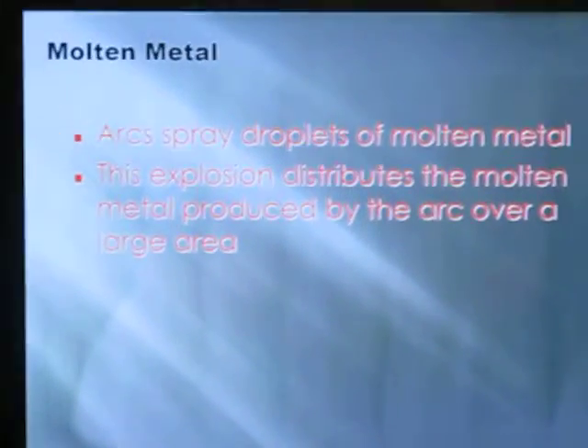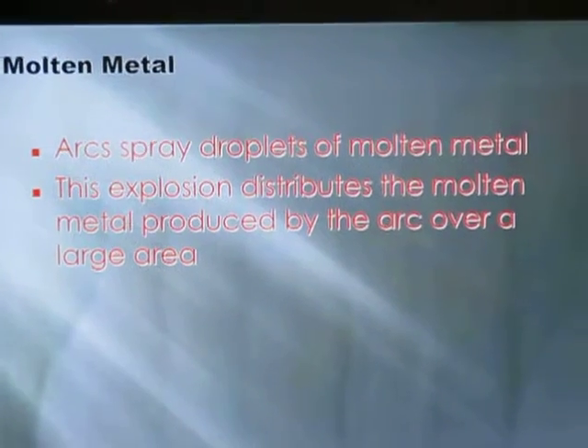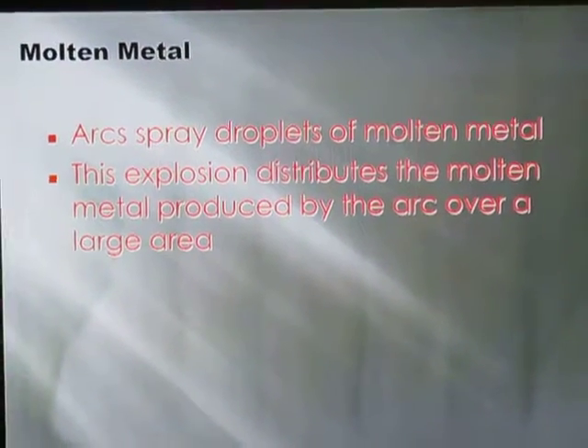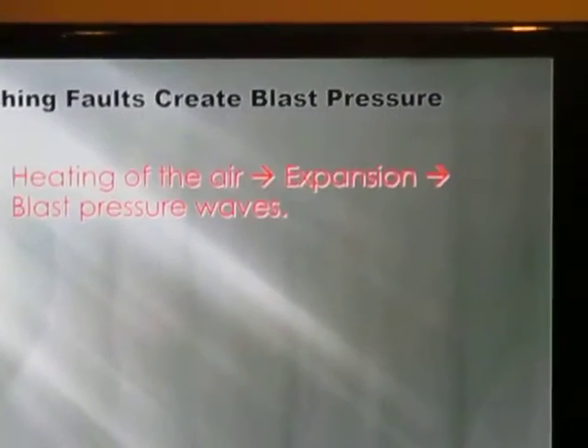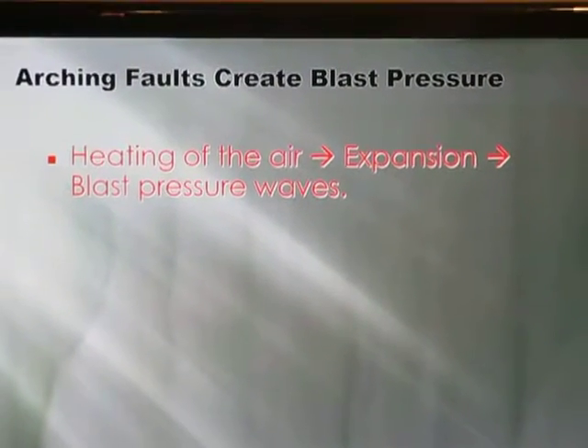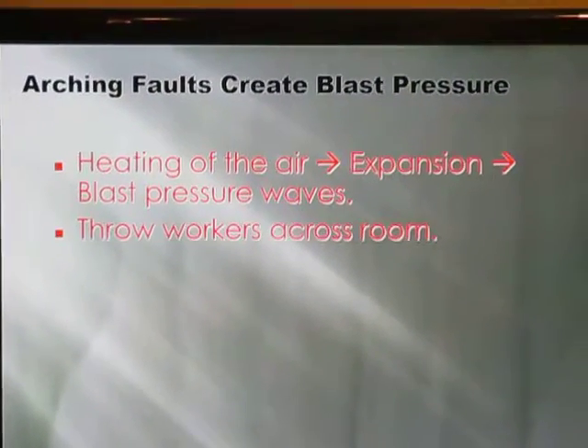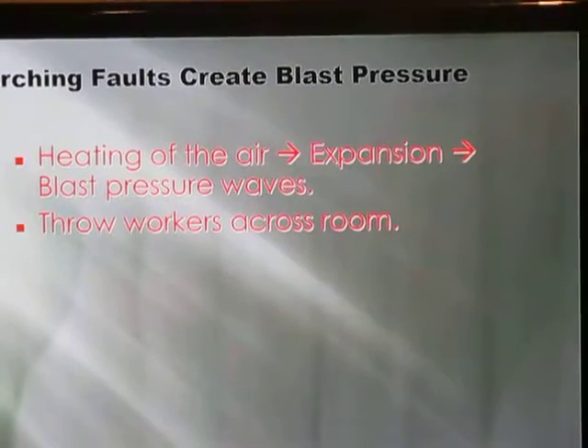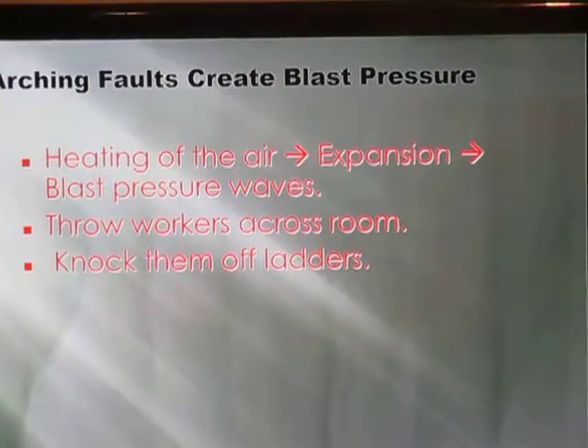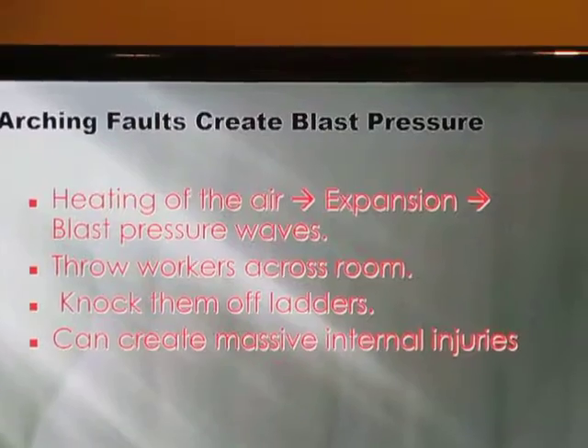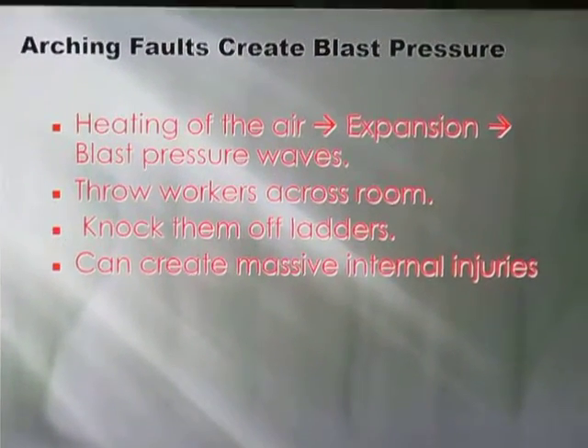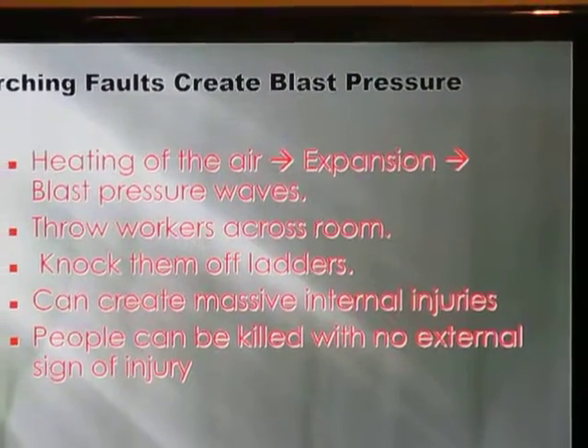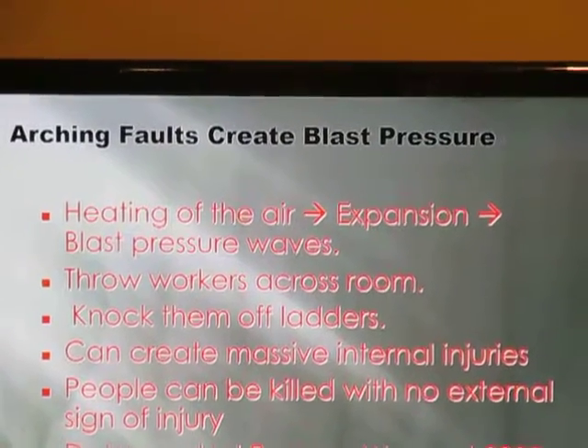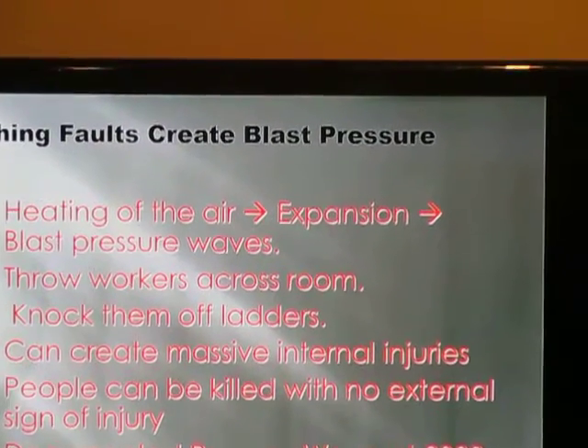Molten metal. Arc sprays drops of molten metal. This explosion distributes the molten metal produced by the arc over a large area. The heating of the air, expansion, and the blast pressure waves. It's known to throw workers across the room, and it knocks them off ladders. It can create massive internal injuries without any signs of outside injuries. And they've documented these at 2,000 psi.